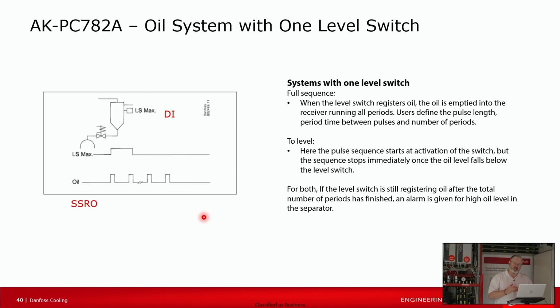And there's a sequence it runs through, which we'll look at in a little while, but it's going to pulse that valve on and off a given number of times in a given time period. And then once it runs through that emptying sequence, it'll stop. Then you'll just wait until the next time the high level switch is tripped. You'll run through the emptying sequence again, and you just do that in perpetuity.